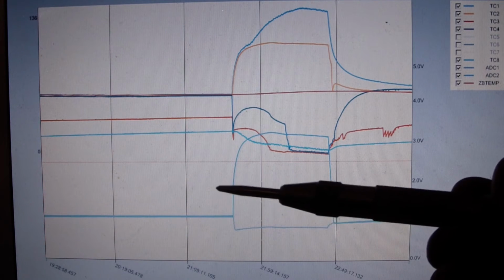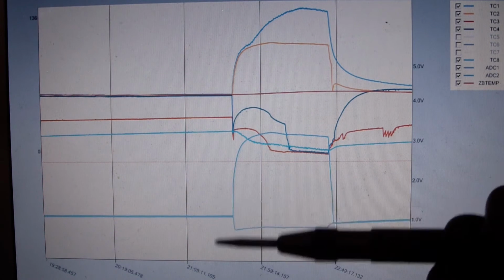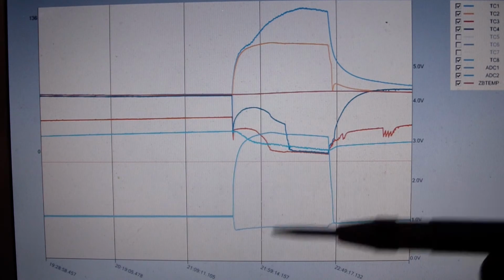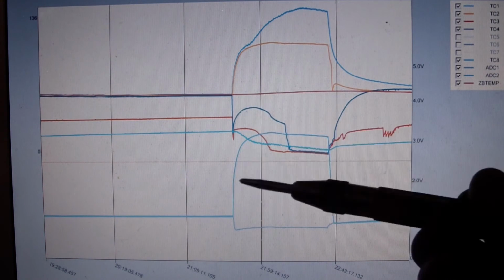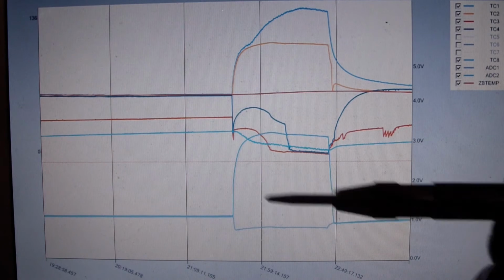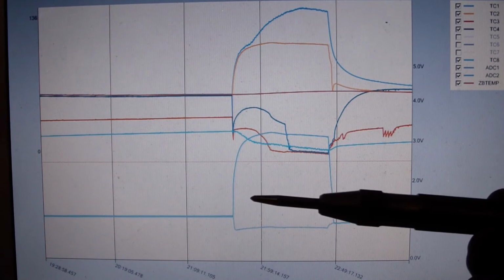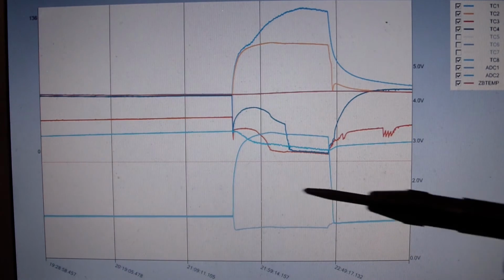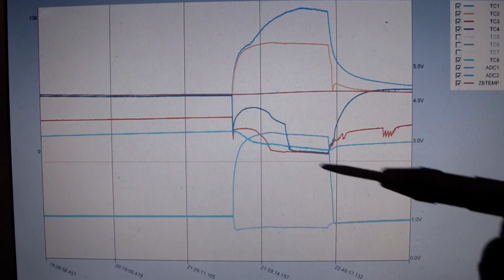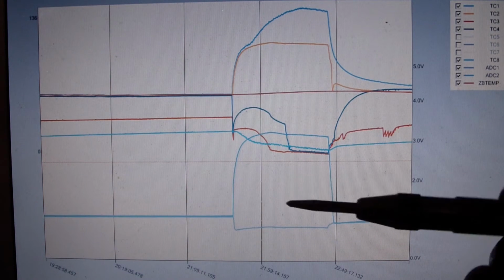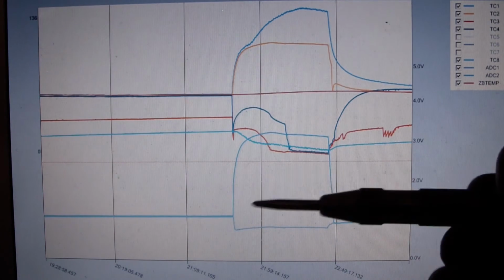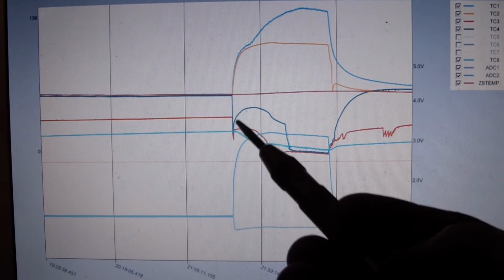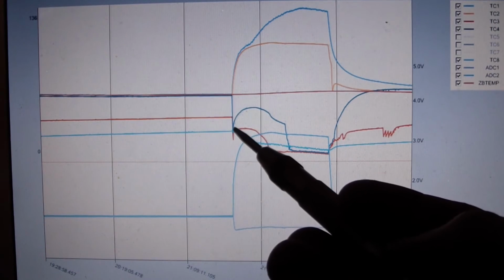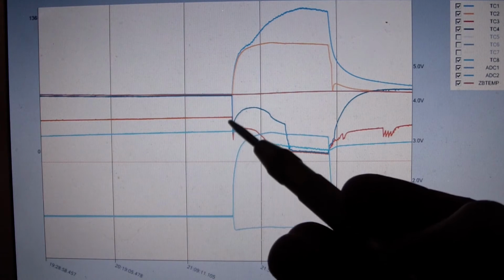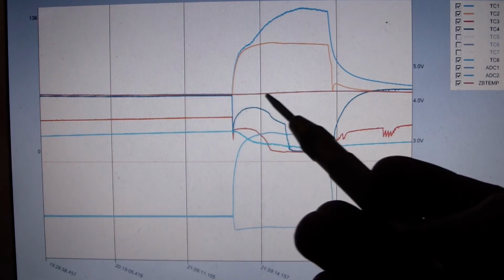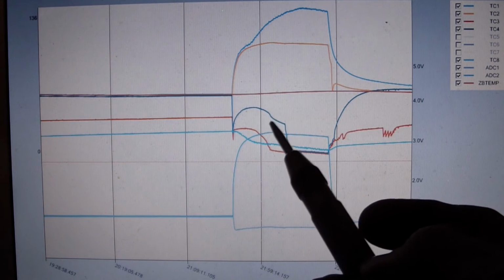How effectively the evaporator conducts heat into the refrigerant is not a constant by any means. At the beginning of the run, assume that it has a lot of liquid around it that was melted off from ice during the previous off cycle. So there's plenty of heat load to be had right there in the immediate surroundings of the copper tubing. And that's why in the very beginning we get the sudden drop in suction line temperature, but then it quickly rises again.